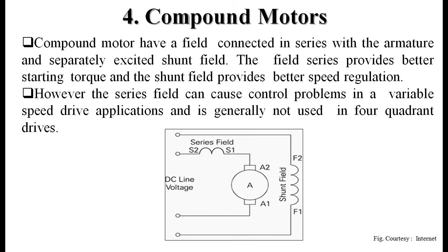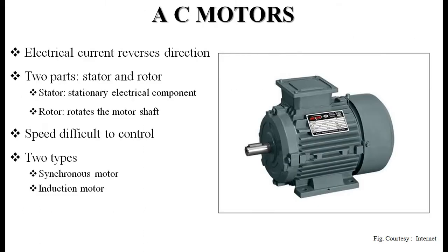Compound motors have a field connected in series with the armature and a separately excited shunt field — so both a series field and a shunt field are present. The series field provides better starting torque and the shunt field provides better speed regulation, combining the advantages of both motor types. However, the series field can cause control problems in variable speed drive applications and is generally not used in four-quadrant drives.